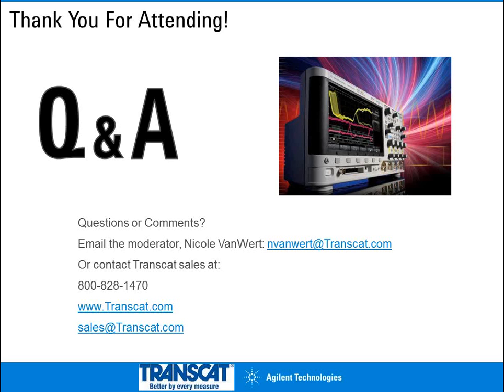Okay. Third question. Why is your mask test mode so much faster than the other manufacturers? Good question. So we do our mask testing in hardware. So that oscilloscope on a chip, that custom ASIC that we have designed, everything's done in real time as opposed to a software post-processing routine. So it increases the speed of almost everything we do across the board.